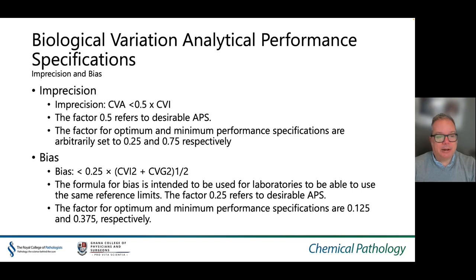Bias specifications can be set at less than 0.25 times the square root of the sum of the squares of CVI and CVG. The formula for bias is intended to allow laboratories to use the same reference limits. The factor 0.25 refers to the desirable analytical performance specification, and the factors for optimum and minimum performance specifications are 0.125 and 0.375 respectively. The choice of which factor to use depends on the intended use.